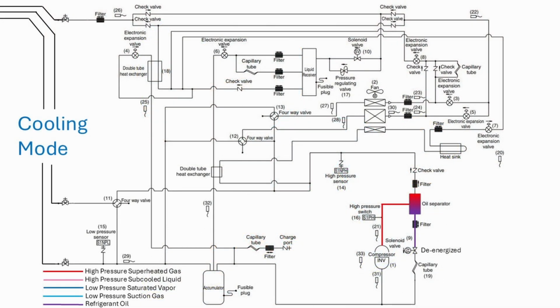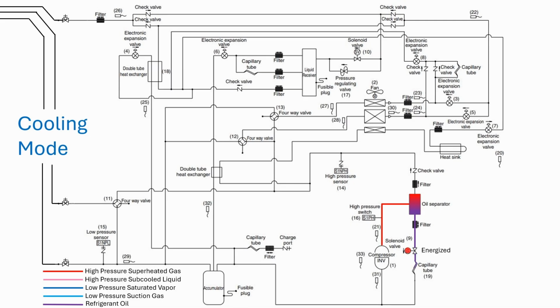When the oil leaves the oil separator, it passes through a filter and then a solenoid valve. The solenoid valve is activated or opened when the system goes into oil recovery mode. Oil recovery mode is triggered by the system controller when the compressor runs a specific amount of time at lower frequencies, which is where the oil separator is the least effective. The oil then passes through a capillary tube to remove any liquid refrigerant that could be trapped in the oil so that it doesn't damage the compressor.